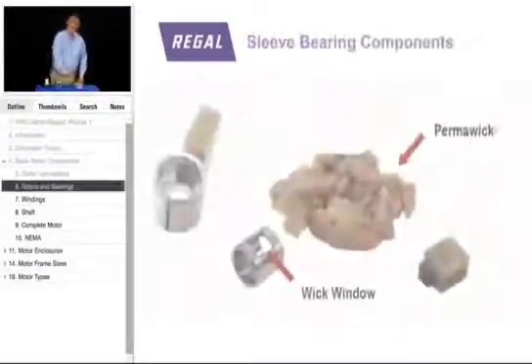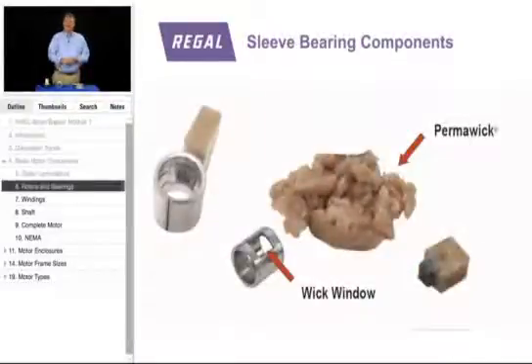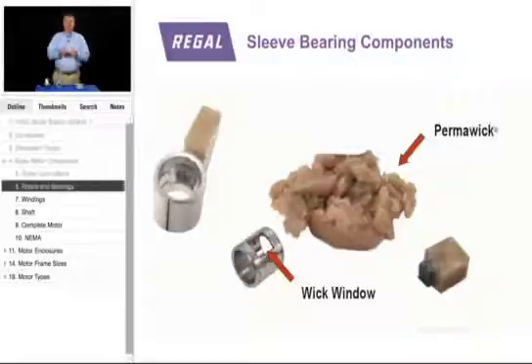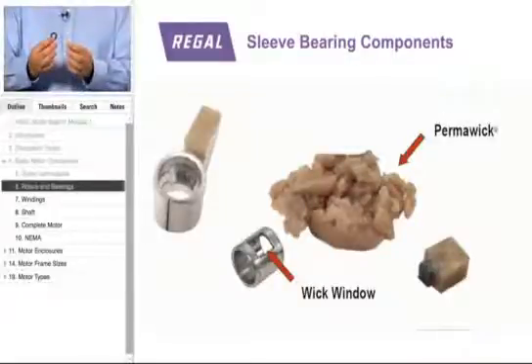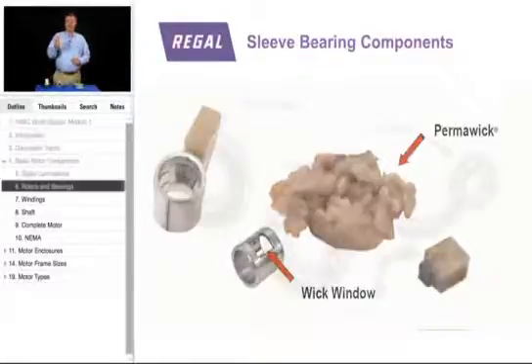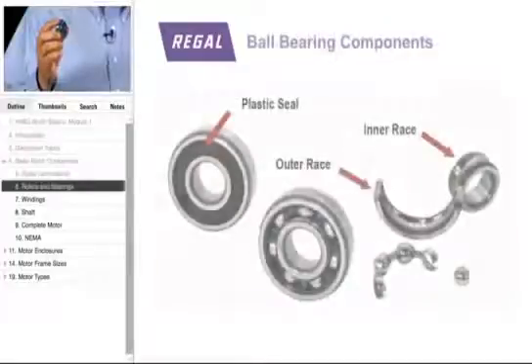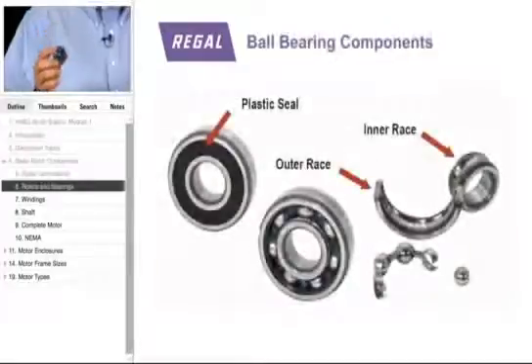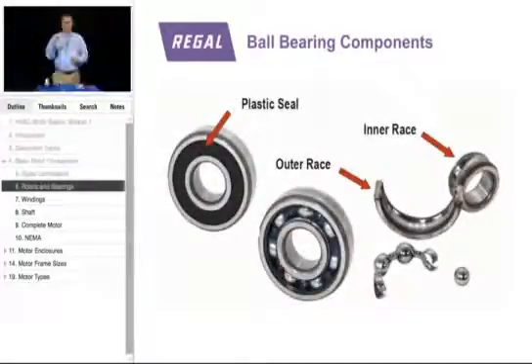We use two types of bearing systems in HVACR motors. Sleeve bearing components have a wicking material that puts a thin sheet of oil on the shaft to allow the motor to turn. Or a ball bearing motor — we use these when there are more radial or axial loads against the shaft that help the motor turn without binding up.